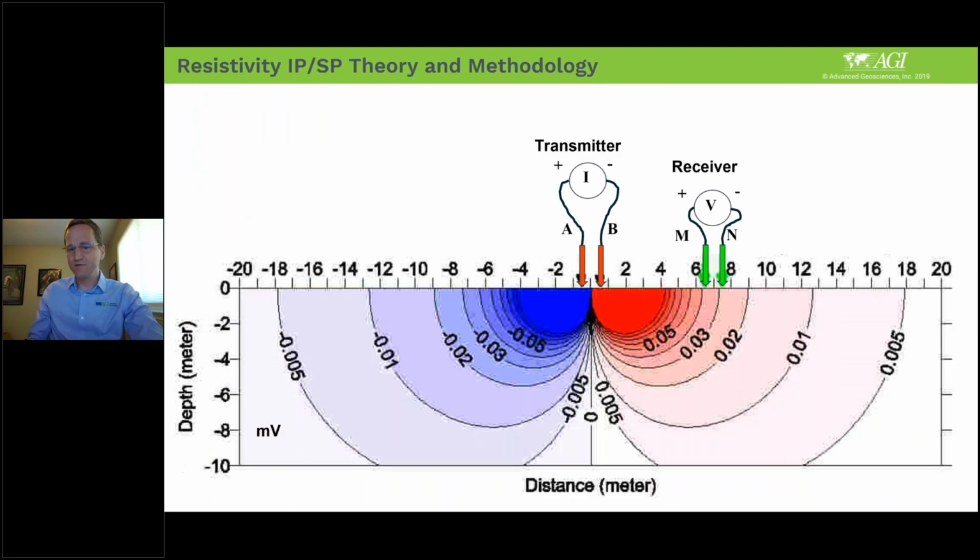These are the voltages. You can see these are very small. That's why our system needs such good isolation, and why we stress that in the design. The receiver is very sensitive, and the transmitter itself, on the scale of small testers, like the Megger or some of these other small handheld ones, ours is a very large transmitter, 200 watts on the SuperSting, or 50 watts on the Mini Sting.